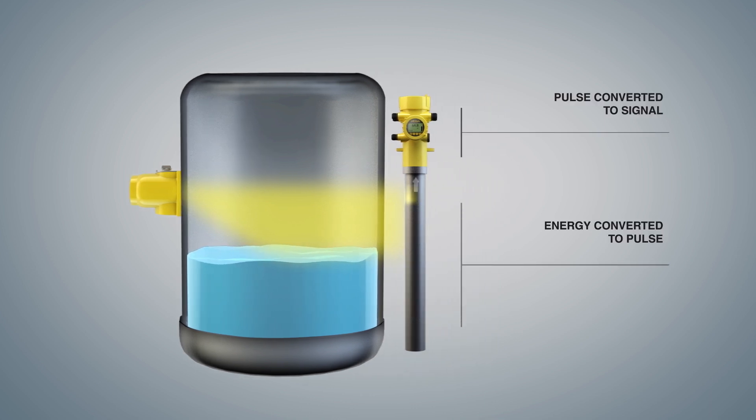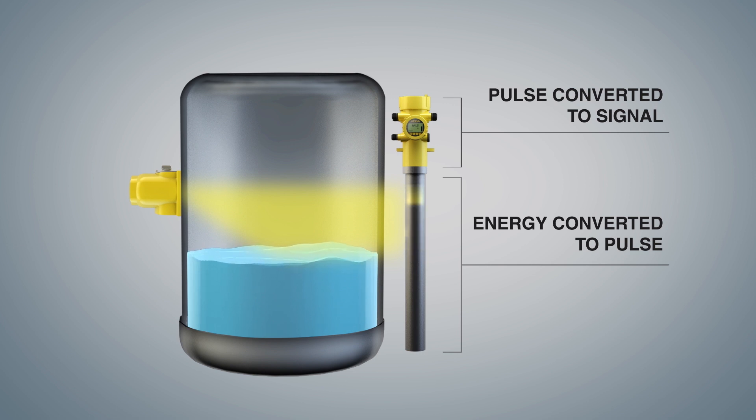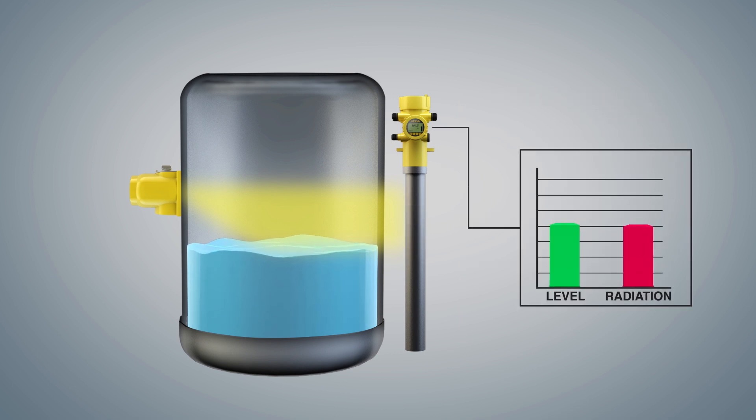When gamma energy reaches the detector, it is converted to a pulse of light that transmits until it reaches the photomultiplier, where it is amplified and processed into an electronic signal. As mass increases in the process, less radiation reaches the detector. The detector electronics use the gamma reading to infer a measurement and outputs the value.